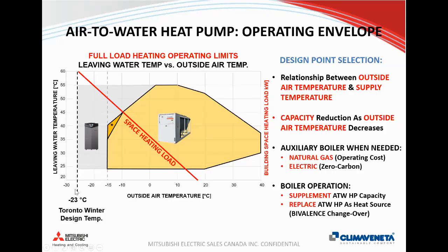And as it gets warmer from our design temperature, we typically have less heat loss from the building, meaning we don't have 100% load. And eventually, as it gets into the warmer temperatures, between 10 and 20 degrees, in a two-pipe system, for example, those will be just changed over. So typically in April or May. It's not necessarily a fixed temperature, but generally, the warmer it is outside, the less heat losses you have. So the less requirement to add heat to the building is required from either a boiler or a heat pump system.